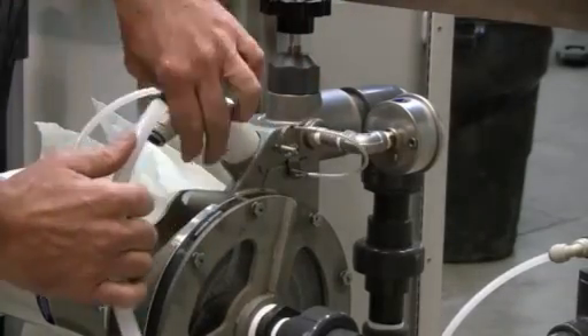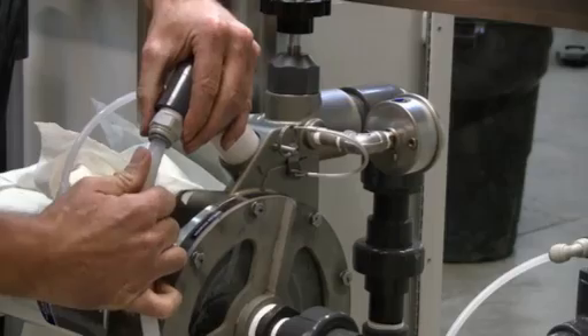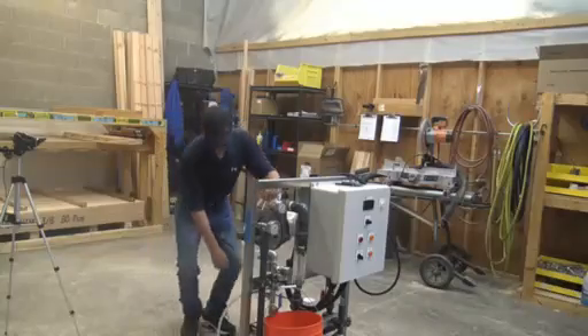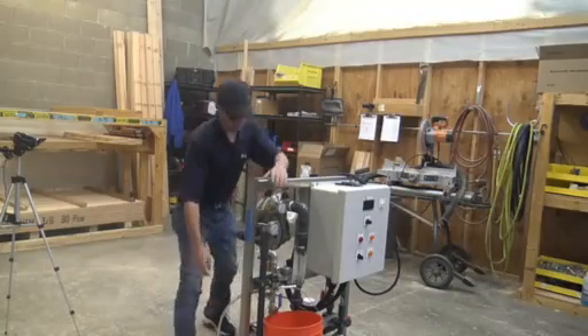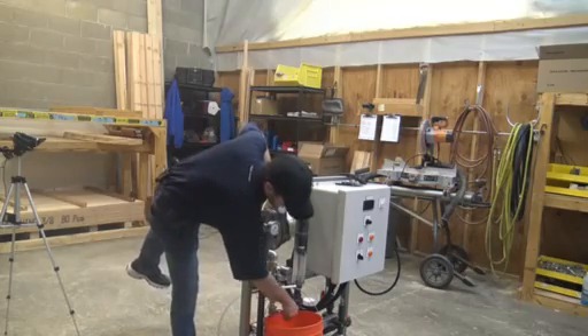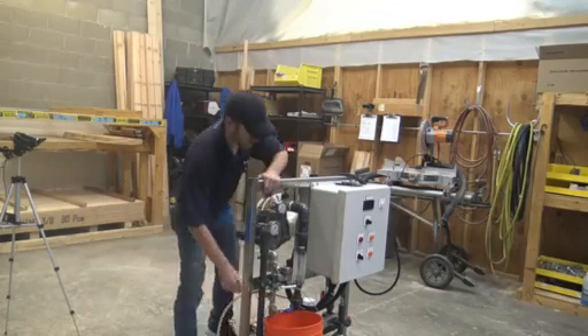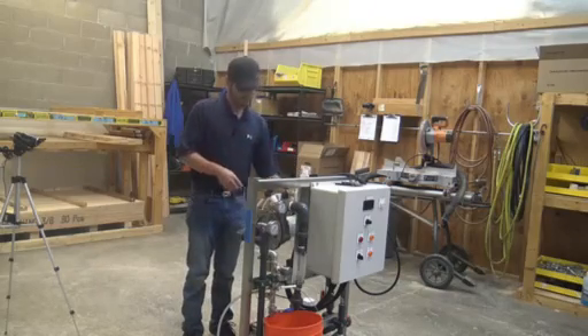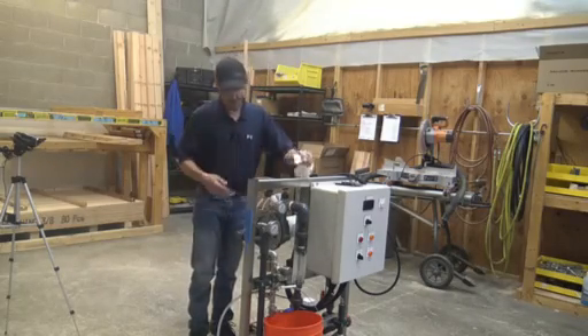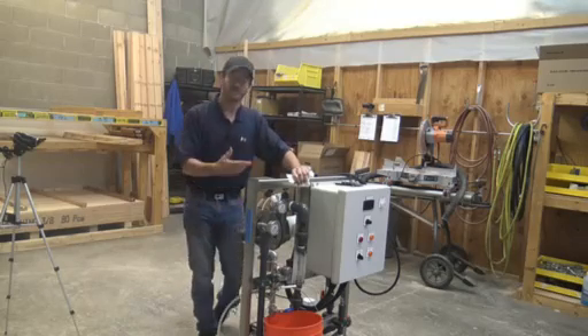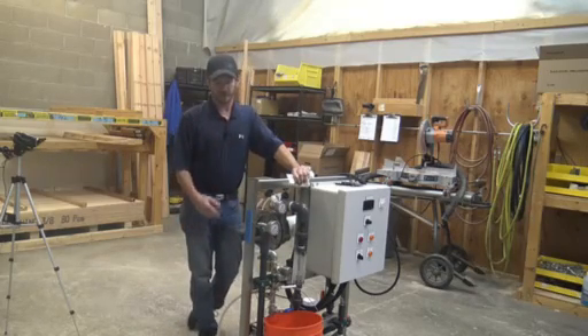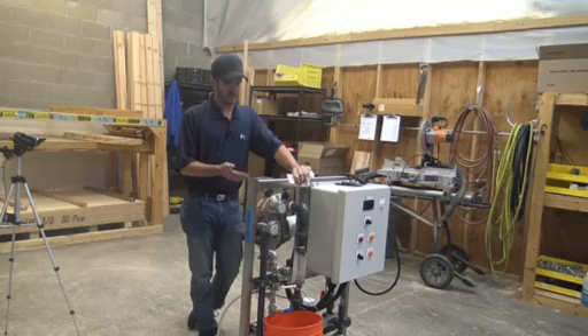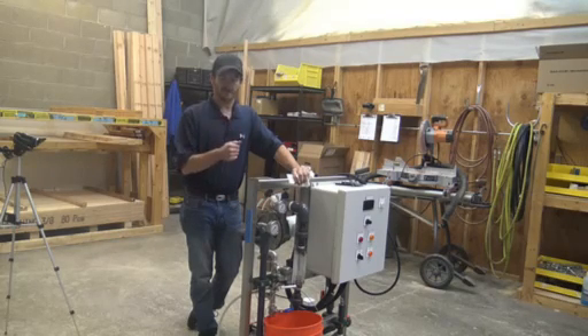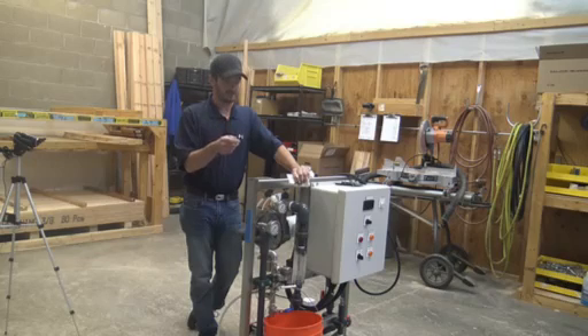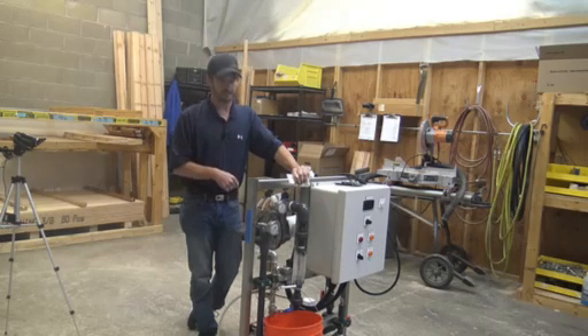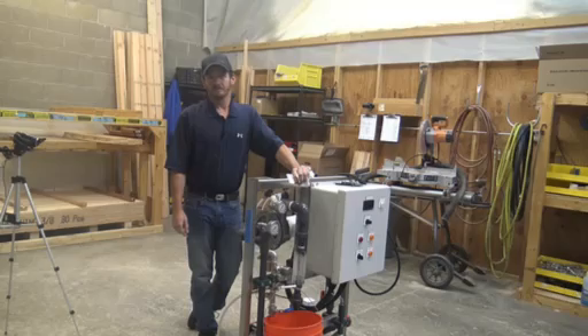Hook up your polymer line and make sure all your valves are closed. So that one's closed and that one's closed. And depending on your system, when you start up the first time after you do all this, you might have to run it a couple times. It might give you a low flow on the polymer alarm, but just acknowledge the alarms, reset them, and turn it back on, and it should be fine. That concludes our video. Thank you.